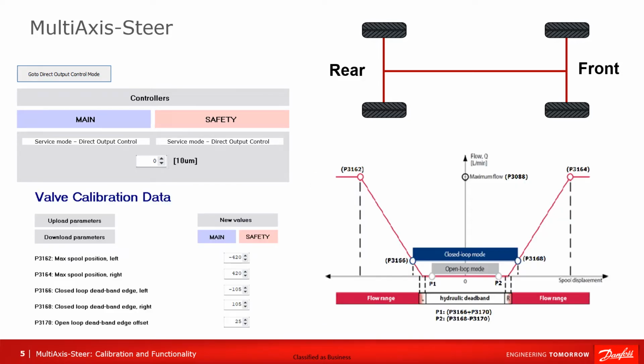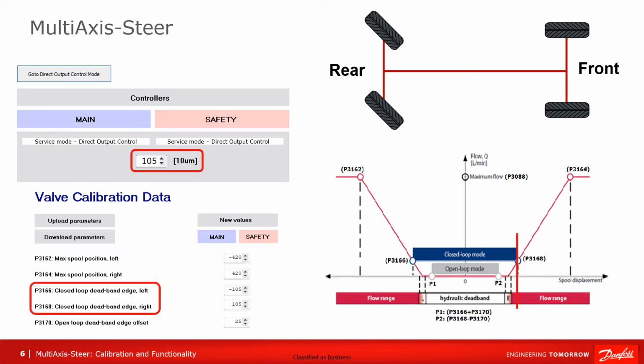In the standard firmware, the spool can be calibrated by entering spool calibration mode and turning the steering wheel to engage the auto spool calibration. However, often this will not work for multi-axis. In this case, the spool can be calibrated manually using the direct output, status messages, and valve calibration data pages. To find the deadband edges, the spool position should be decreased using the direct output control mode until the wheels will no longer move at a constant velocity. Once the wheels stop moving smoothly, raise this value slightly so that the wheels will just move at a constant velocity. This is your closed loop deadband edge and should be entered into the valve calibration data page.